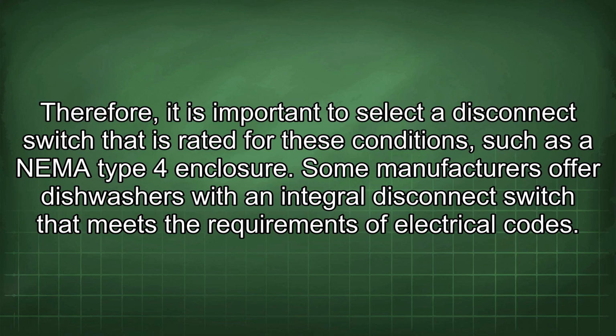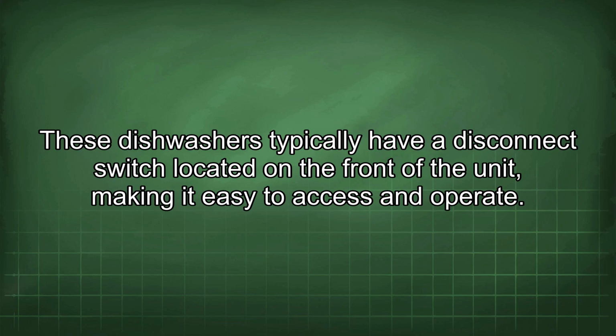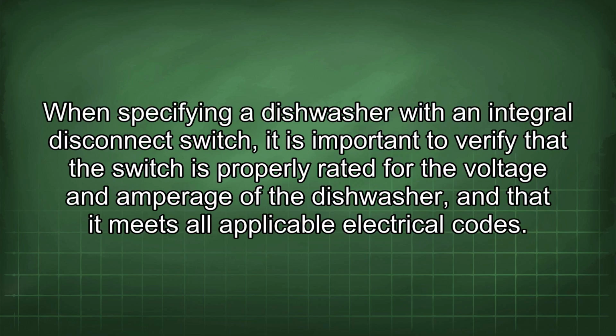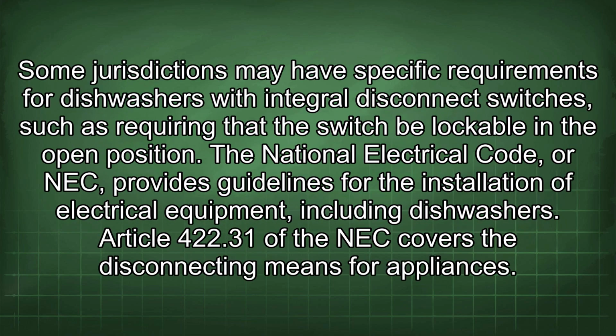Some manufacturers offer dishwashers with an integral disconnect switch that meets the requirements of electrical codes. These dishwashers typically have a disconnect switch located on the front of the unit, making it easy to access and operate. When specifying a dishwasher with an integral disconnect switch, it is important to verify that the switch is properly rated for the voltage and amperage of the dishwasher and that it meets all applicable electrical codes. Some jurisdictions may have specific requirements for dishwashers with integral disconnect switches, such as requiring that the switch be lockable in the open position. The National Electrical Code, or NEC, provides guidelines for the installation of electrical equipment, including dishwashers.